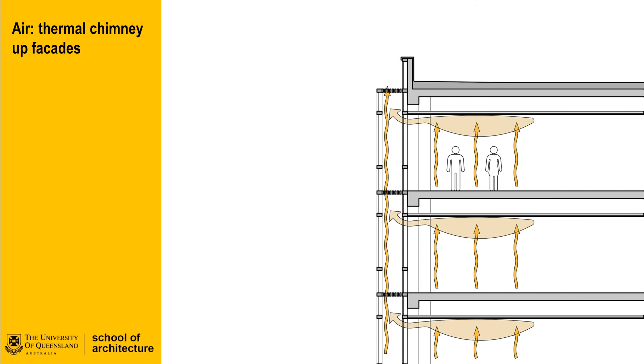The effect of natural buoyancy can also be used on the external facade to induce airflow up and outside the building without the problems of excessive natural airflow inside the building. The use of double facades has increased in popularity in the past two decades, especially in Europe and now in the United States and Australia. The chimney or stack effect on the outside of the building can be regulated in a number of ways to change the way that the system works seasonally and in different contexts. A stack on the external wall can also help induce airflow inside the building and help with exhausting stale air to the outside.